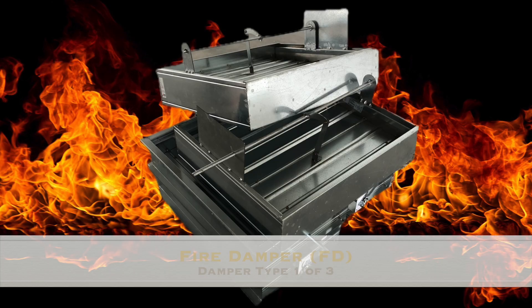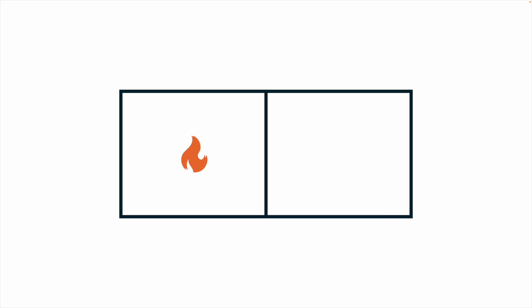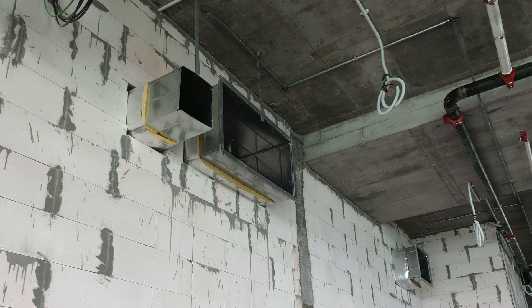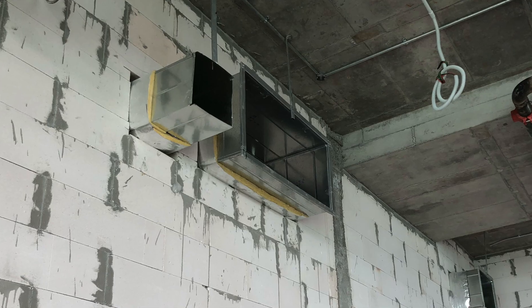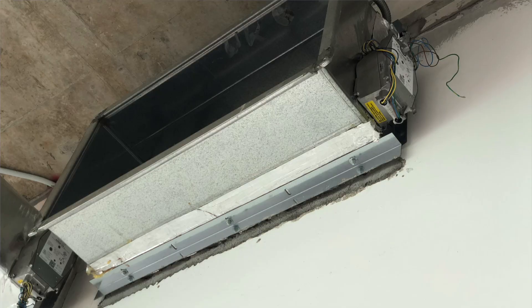Generally we have three types of damper. The first type is fire damper. The purpose of fire damper is to prevent fire and smoke from spreading from one compartment to the other compartment. So fire damper is needed whenever we have a duct penetration — that means your ducting will run through a wall. At the wall section there, you need to install a fire damper.